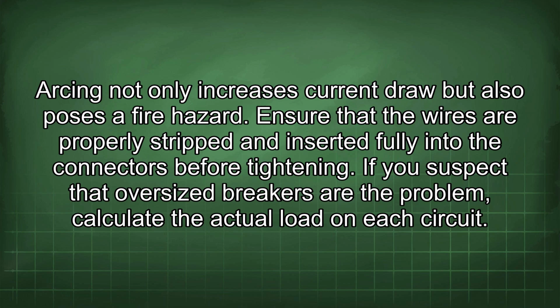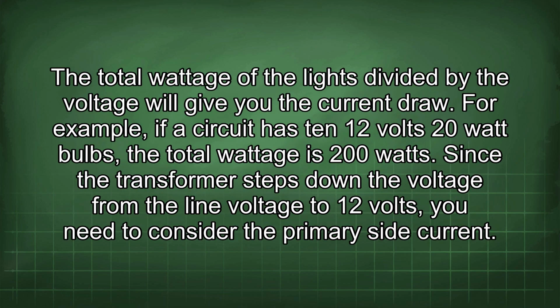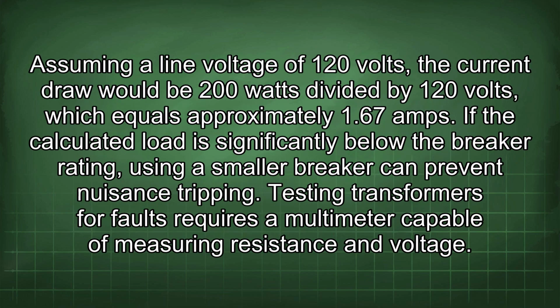If you suspect that oversized breakers are the problem, calculate the actual load on each circuit. The total wattage of the lights divided by the voltage will give you the current draw. For example, if a circuit has 10 12-volt 20 watt bulbs, the total wattage is 200 watts. Since the transformer steps down the voltage from the line voltage to 12 volts, you need to consider the primary side current. Assuming a line voltage of 120 volts, the current draw would be 200 watts divided by 120 volts, which equals approximately 1.67 amps. If the calculated load is significantly below the breaker rating, using a smaller breaker can prevent nuisance tripping.